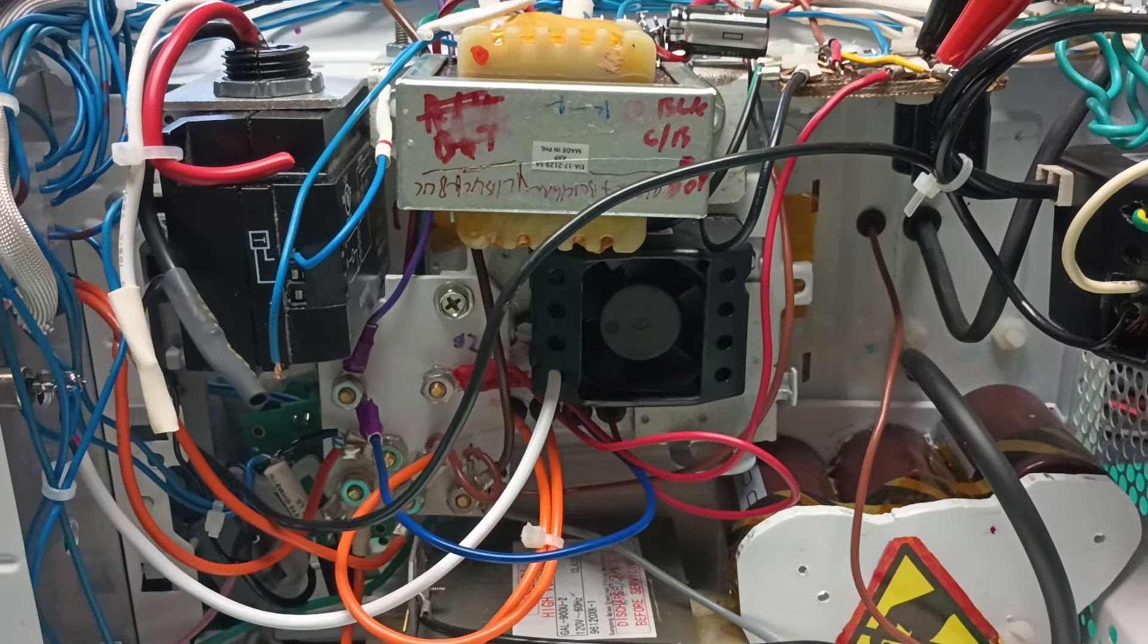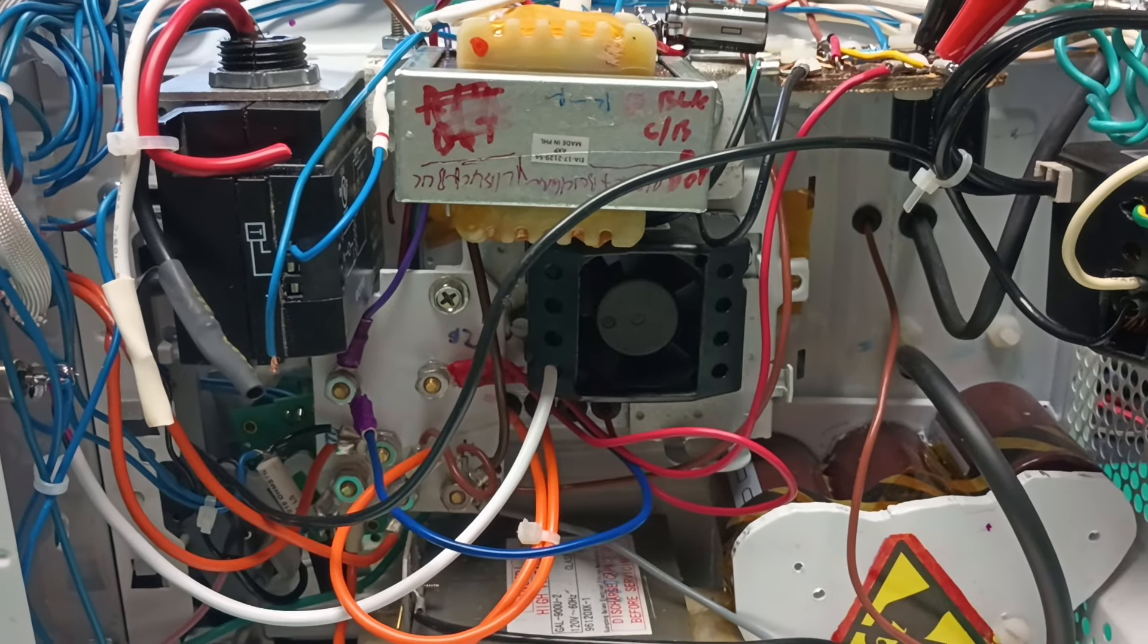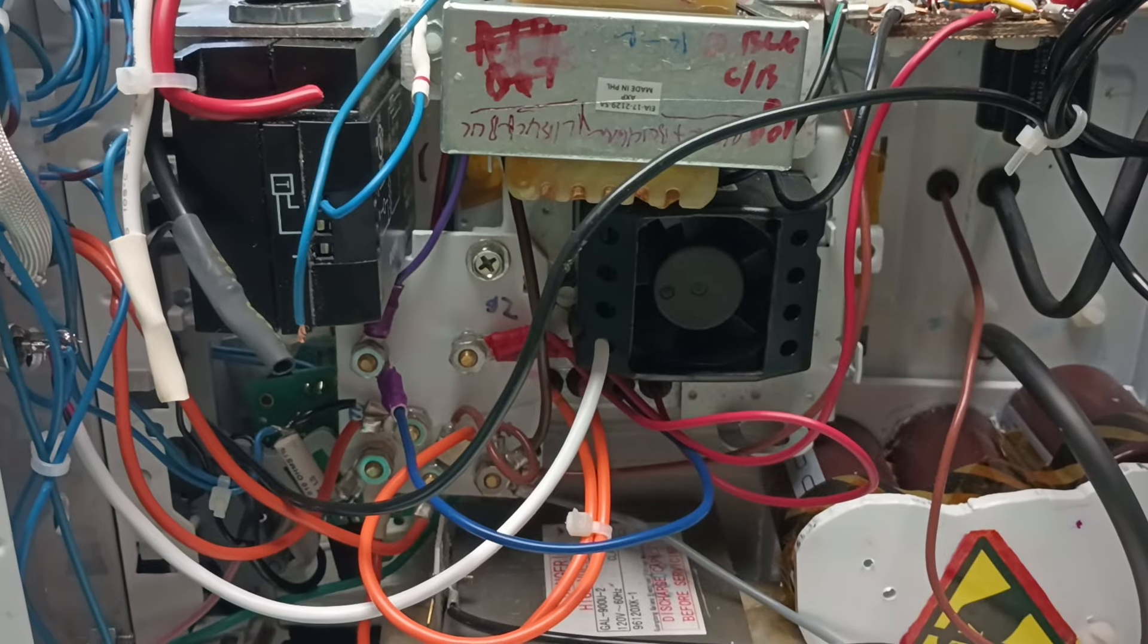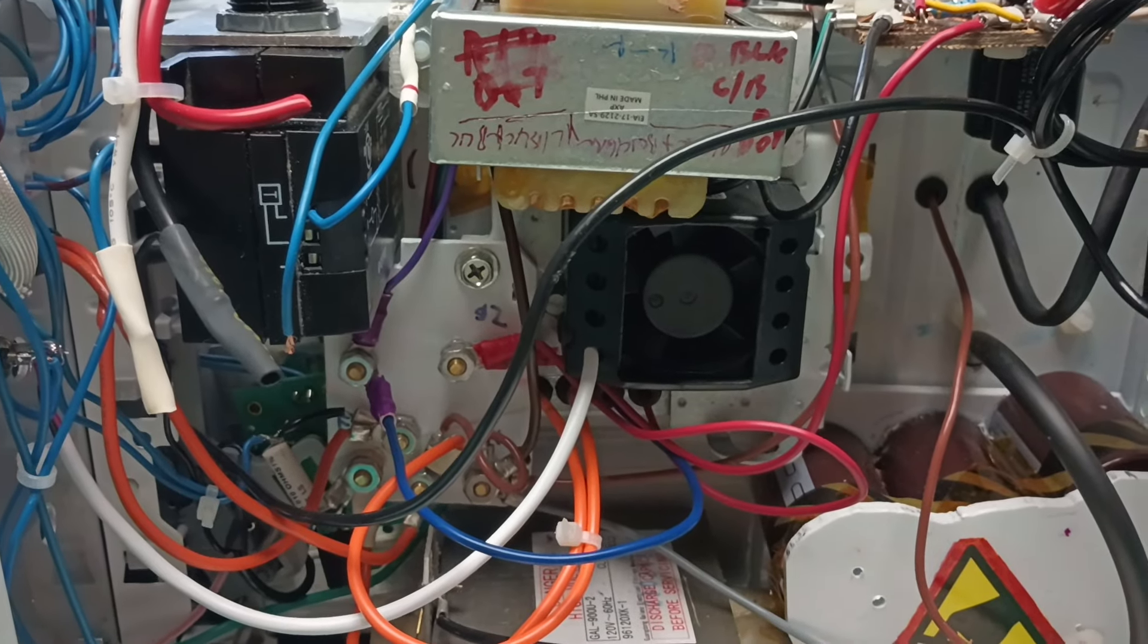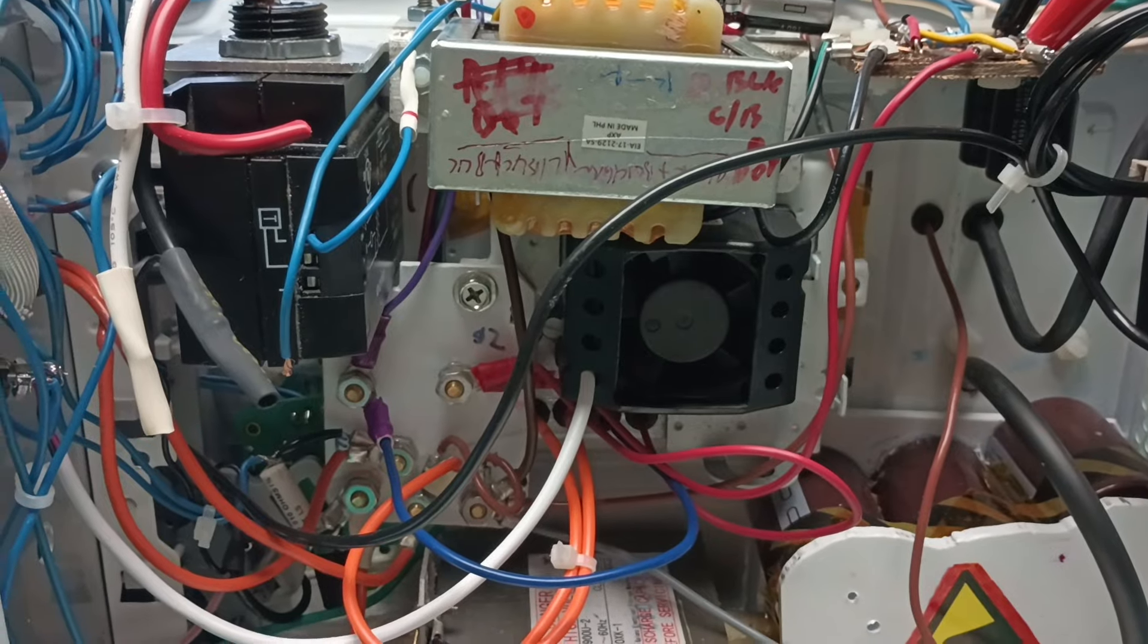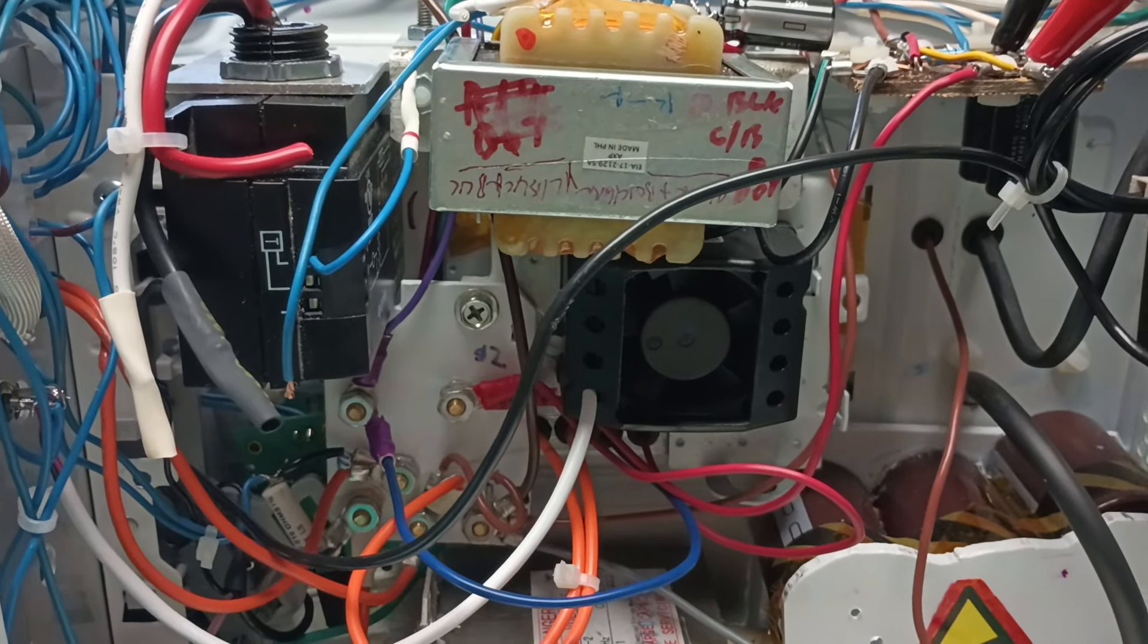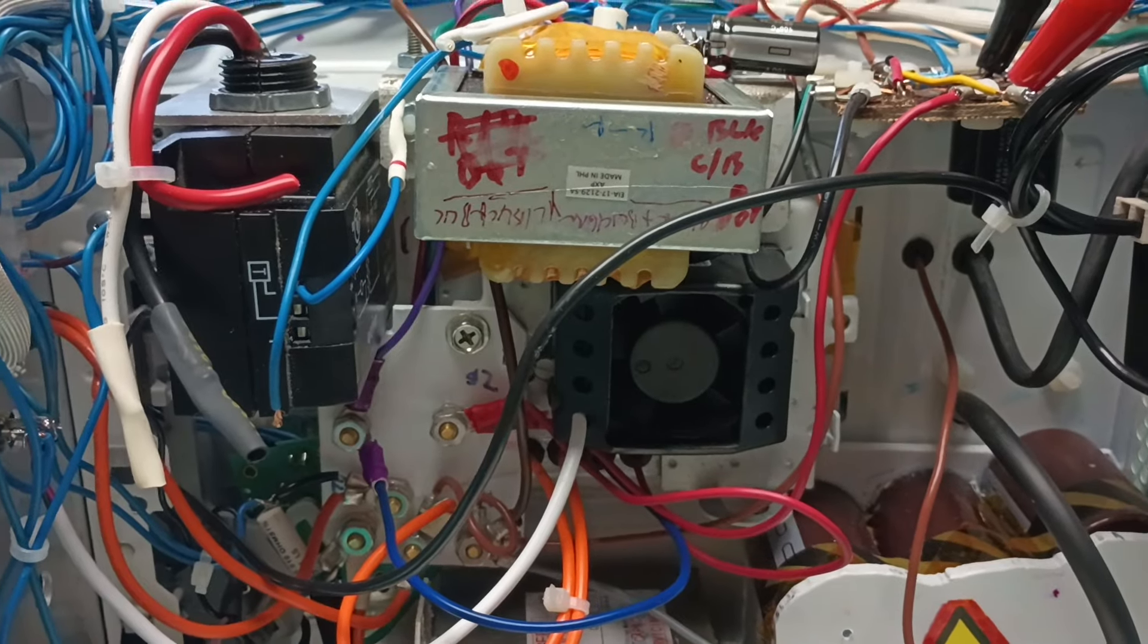And it's something I've never seen happen in 50 years of farting with this stuff. Transformer buzzing means something's drawing a whole lot of current. That's a 50-watt transformer, the load's only 10 watts, so something is sinking a bunch of current making the transformer buzz, or something's out of balance.